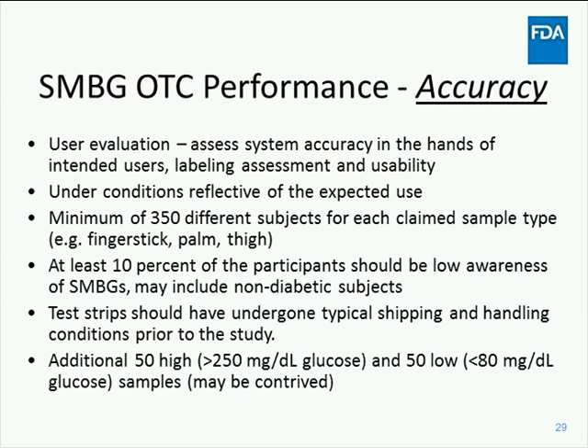We recognize that the user study may not provide a sufficient evaluation of the device performance of the extreme upper and lower ends of the measuring range. Therefore, if natural patient samples are not obtained at the extreme ends of the measuring range, then additional samples may be contrived by spiking or glycolysis to obtain an additional 50 samples with high glucose concentrations greater than 250 milligrams per deciliter and 50 samples with low glucose concentrations less than 80 milligrams per deciliter.